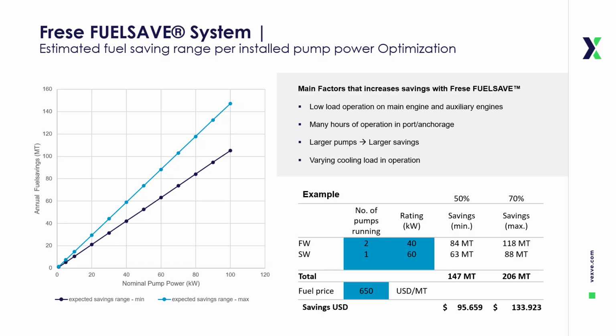The savings potential of the Frese FUELSAVE system depends on several key operational factors. First, vessels that operate for extended periods at low main engine load or with auxiliary engines running at partial capacity will see the largest benefit. This is because pump systems are often oversized for real-world operating conditions, and FuelSave optimization aligns energy use with actual demand. Second, vessels spending many hours in port or at anchorage gain additional savings. During these periods, cooling water demand is lower, yet conventional systems still consume significant pump energy. FuelSave reduces this wasted energy.